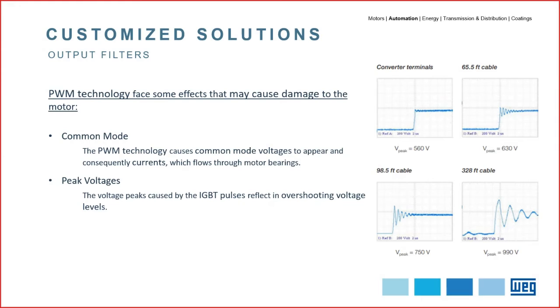The voltage peaks caused by the IGBT pulses result in overshooting voltage levels. When the cable connecting the VSD and the motor is long, the reflection effect amplifies the overshoot, which can cause damage to the motor insulation. The VSD creates extremely fast rise times, or dV/dt, which can also cause issues on the motor insulation and decrease its lifetime.